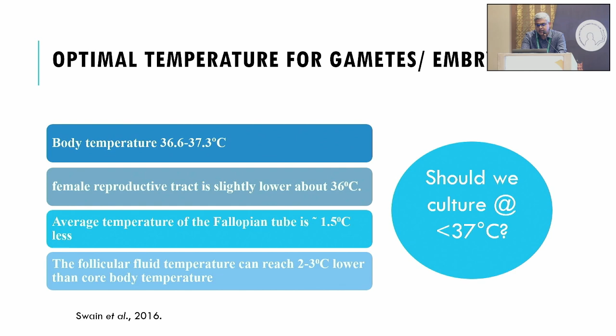So this is where equipment calibration is very important. It's not that you have to check the temperature of one or two pieces of equipment once in a while. You should monitor it very closely. These are the most important equipment that I think most of us know about: incubators, heated stages, warming blocks, refrigerators, and even the ambient temperature should be controlled. It's prudent to employ double or triple control on key equipment, especially the incubators. You can have additional sensors or data loggers, and alarms, depending on your setup.